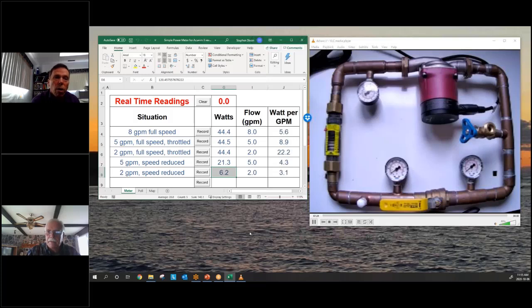And you saw we went from 22.2 watts per GPM to 3.1 watts per GPM for the 2-gallon example. So check your pumps. Low delta T's throttle valve will have the same impact as the demo Stephen just gave us. Yeah, I'm glad you brought up the delta T, because sometimes the delta T problem can lead you back to ultimately another problem or another opportunity as well. So you solve two things in one.